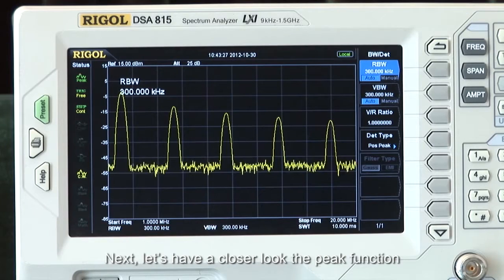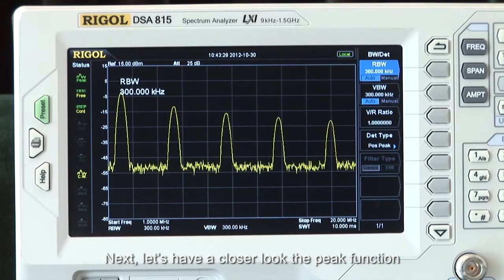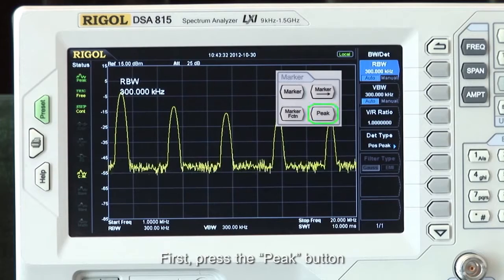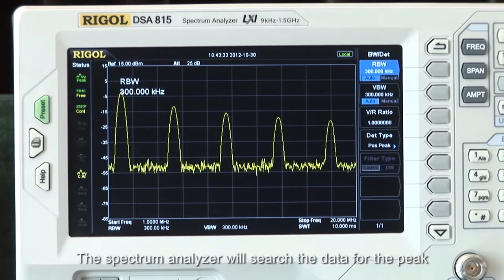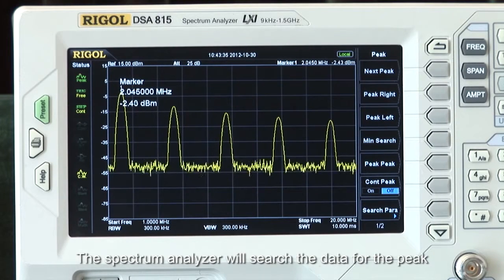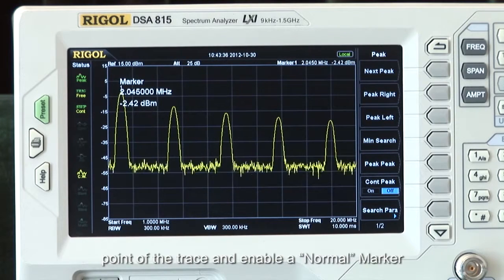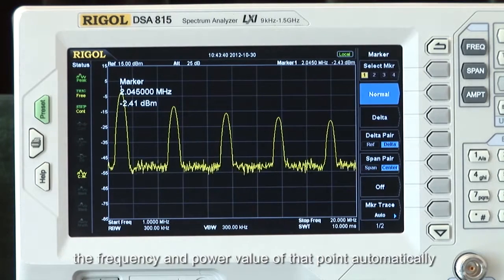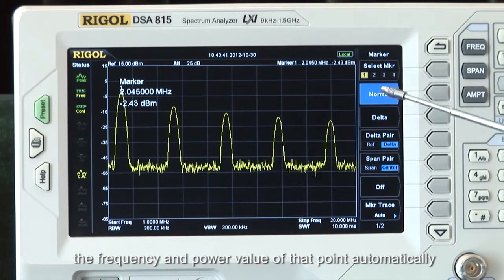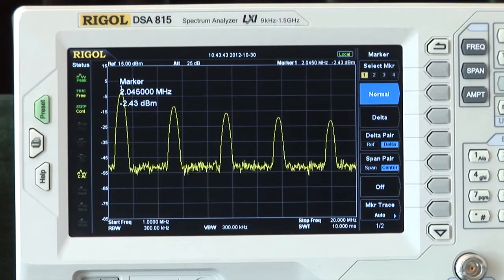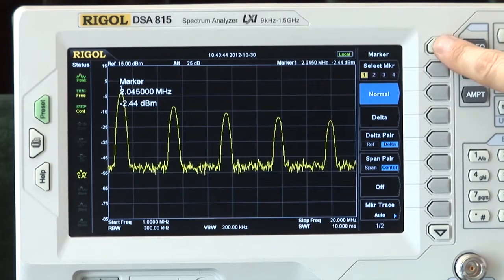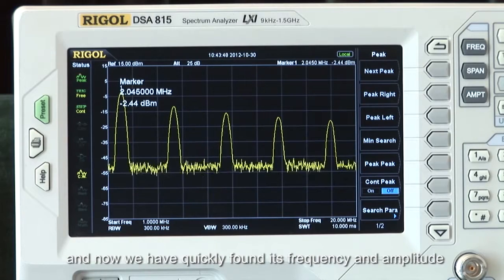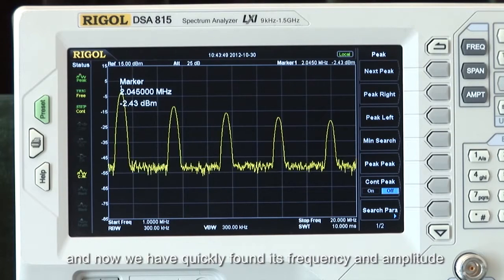Now let's have a closer look at the peak function. Press the peak button. The spectrum analyzer will search the data for the peak point of the trace, and enable a normal marker that will mark the frequency and power value of that point automatically. The first peak is the square wave fundamental, and now we have quickly found its frequency and amplitude.